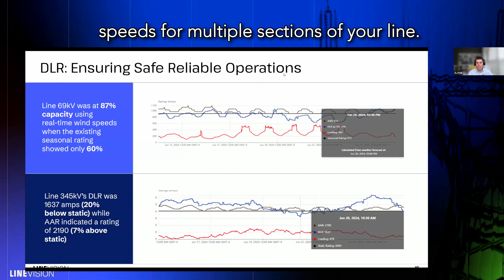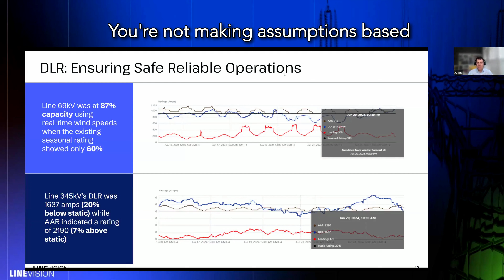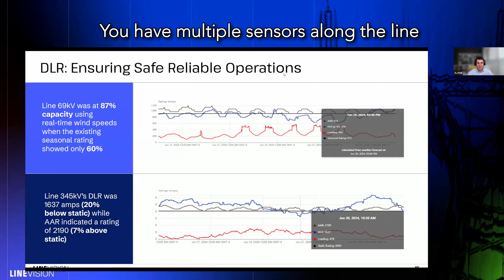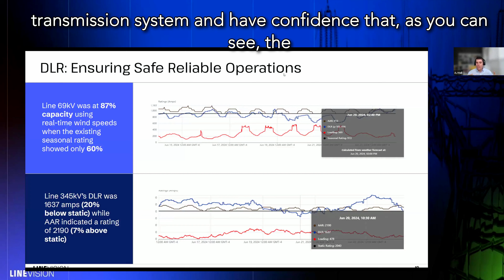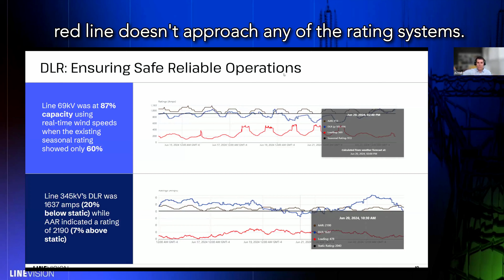You're taking into account real-time wind speeds for multiple sections of your line. You're not making assumptions based on a single ambient temperature. You have multiple sensors along the line monitoring real-time conditions. And so this is a case where operators were able to look at this data at this time of stress on our transmission system and have confidence that, as you can see, the red line doesn't approach any of the rating systems.